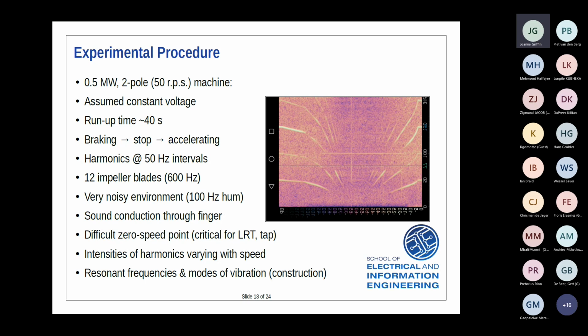What was particularly interesting, I've just made a note here: the intensities of the harmonics vary with speed. Here you can see this harmonic is very loud compared to the others, then this one is loud. As the machine slows down, this harmonic is excited, so that one's loud, and then this harmonic becomes more prominent as the machine slows down more.